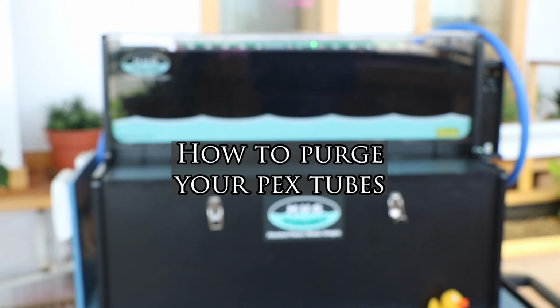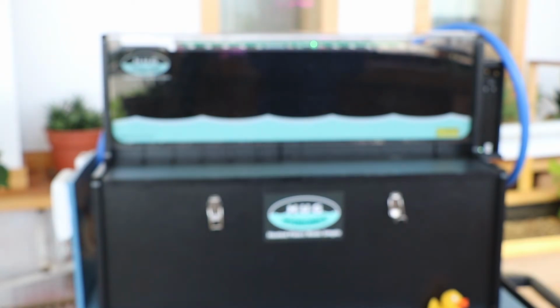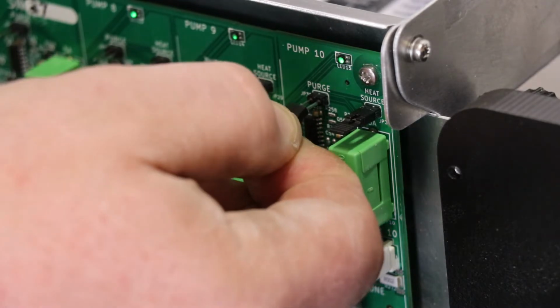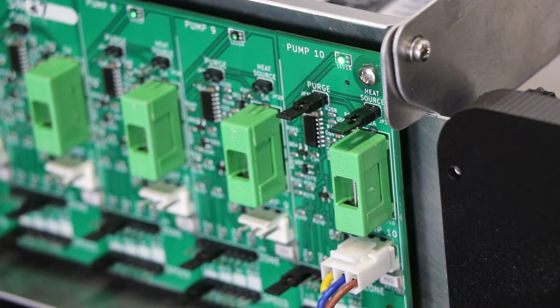Now I'm going to walk you through how to purge the air out of your heater and pipes. Place a spare jumper on the purge pins for pump 10 on the control board to purge the heat source hoses first. The pump light should become bright orange. Let the pump run until gurgling sounds in the water tank cease. This might take several minutes.